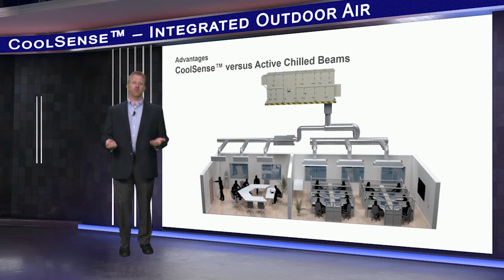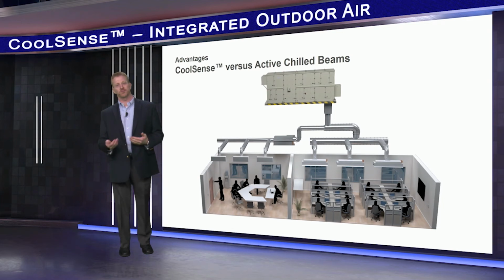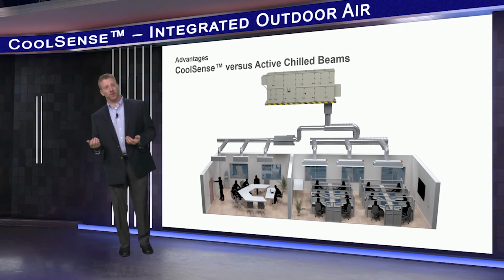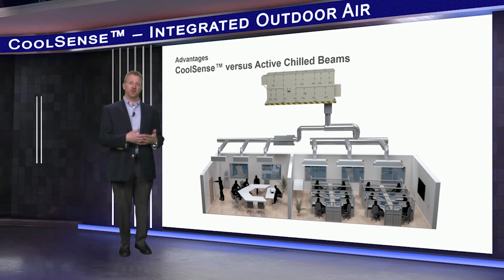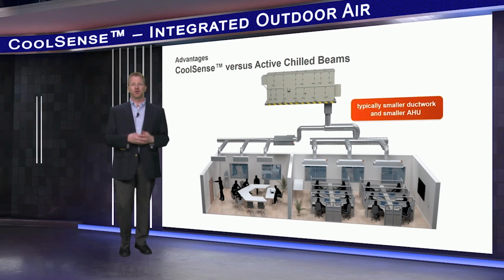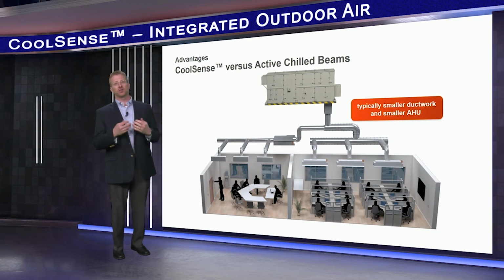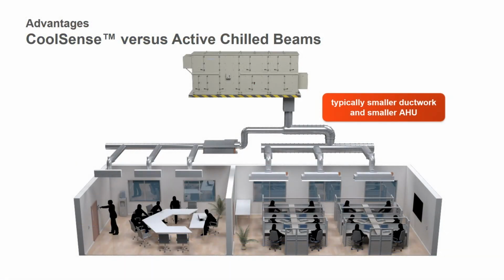As we wrap up, let's compare CoolSense to another sensible cooling system, chill beams, since they are relatively well known and the most similar system type that separates sensible and latent cooling. First, a CoolSense system will typically have smaller ductwork and a smaller air handling unit. Why? Because with CoolSense, the dedicated outdoor air unit and ductwork is typically sized for only the minimum required ventilation air. In contrast, for many applications, the active chill beam system requires the primary air handling unit and the ductwork to be sized to deliver enough primary airflow to also induce sufficient room air for sensible cooling.